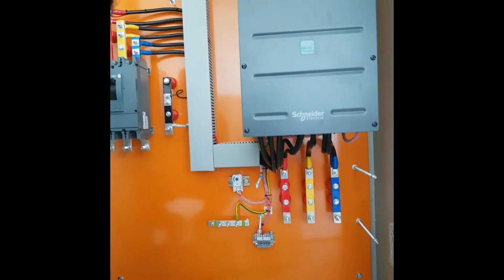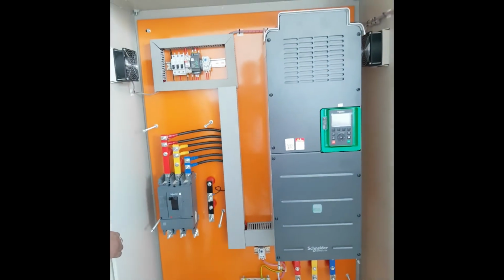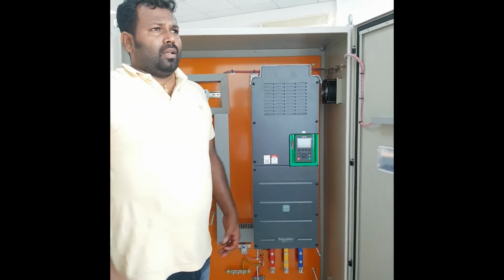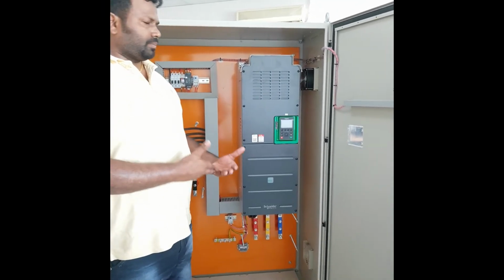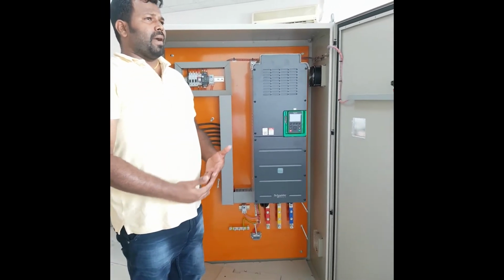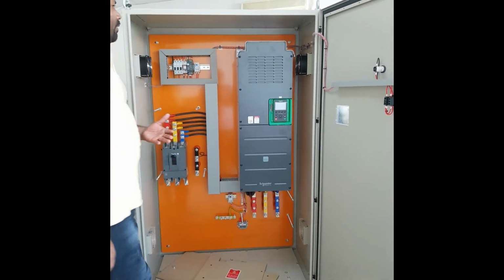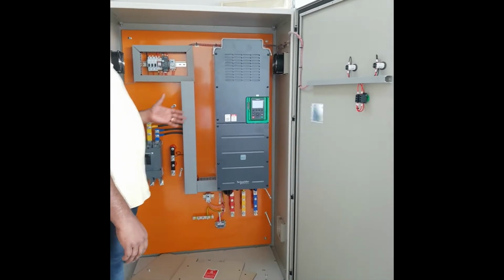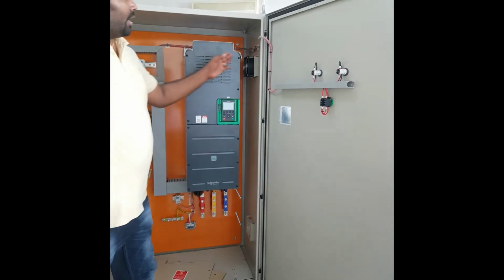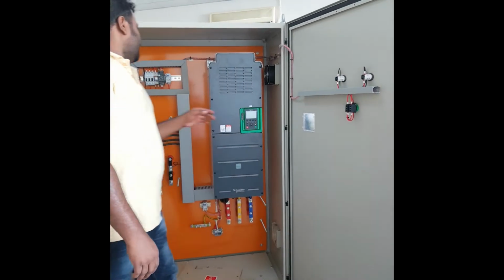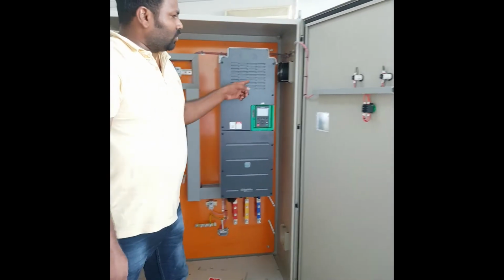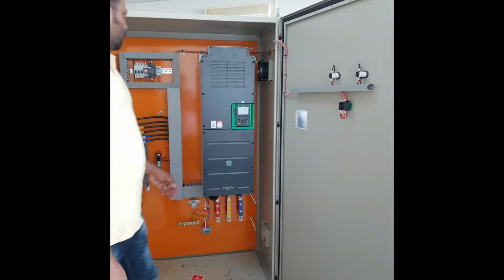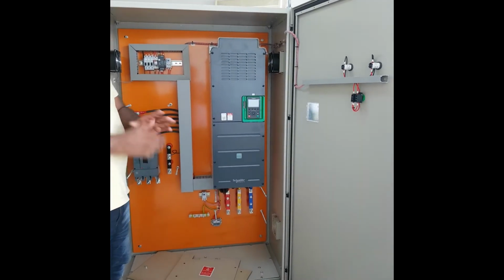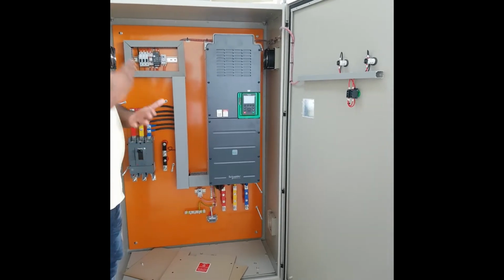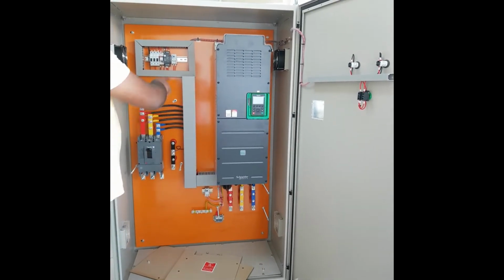Okay, apart from this, since it is a VFD, it will make some heat inside the panel. For this heating, panel ventilation, we have provided 2 exhaust fans on the 2 sides of the panel. Okay, you can see fan 1 and fan 2. Normally, how will these fans run? We have given a temperature thermostat inside the panel.